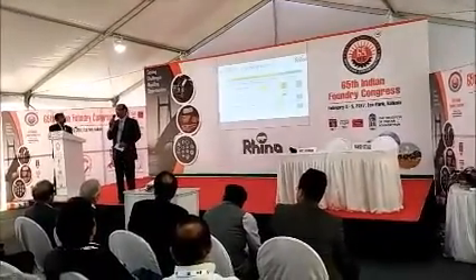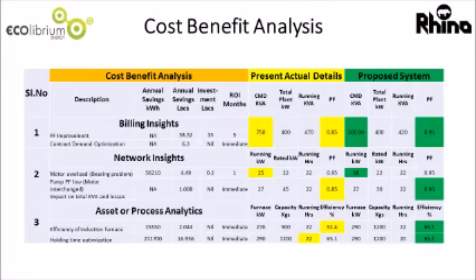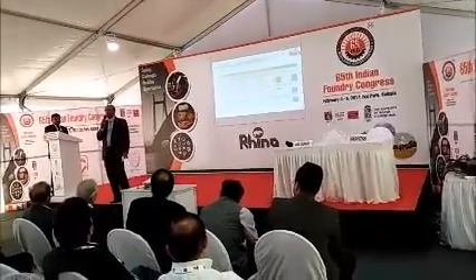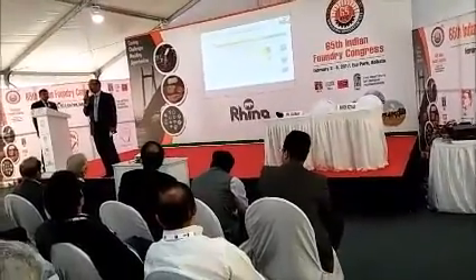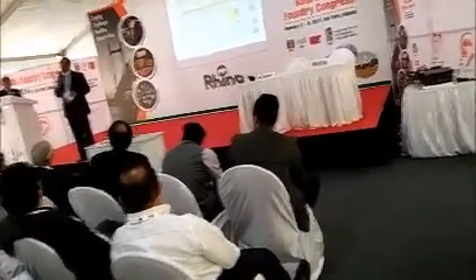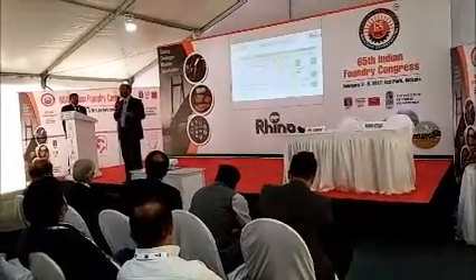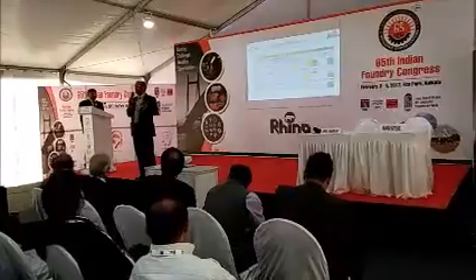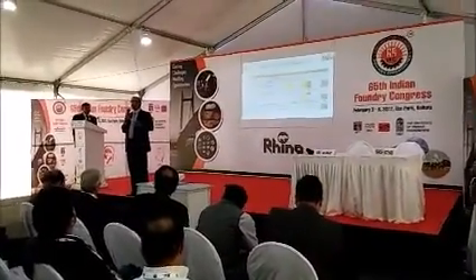For example, in one foundry I have seen that the cold start furnace first heat used to take 2 times or 2.5 times the regular heat. Suppose the regular heat is 1 hour, they used to take 2.5 hours. When I saw the graph, I told them the procedure to make the first heat faster. It should not take more than 20% extra time for the first heat. So if you have data, you can analyze it and then take corrective action. But if you don't have data, you cannot analyze it and you cannot take corrective action.